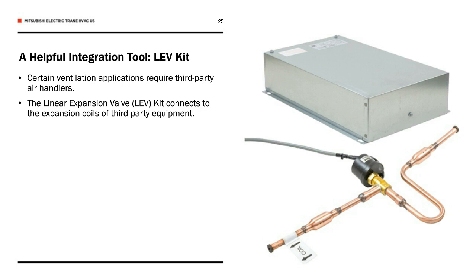Yeah, for sure. Instead, the internals of an existing piece of equipment can essentially be replaced. I've scrolled back to the LEV kit slide. You can see here, the silver box on the top is the controls, the brains of how it works. And the LEV kit itself is incredibly small, and one end of the pipe goes to the coil. It's pretty easy to retrofit and commission in the field to turn an old chassis into a modern air handler that takes the benefit of a VRF outdoor unit that would be placed somewhere else, either on the roof or in the building.